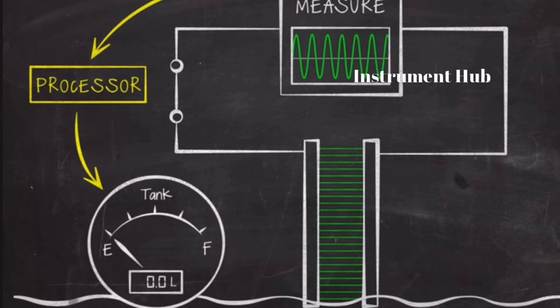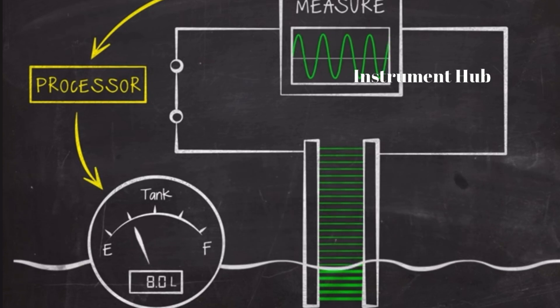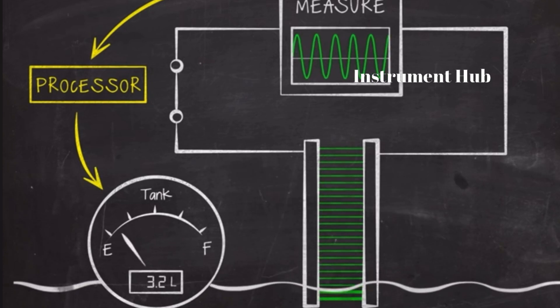This principle is calculated by our controller to process the actual level. For sensor calibration, we perform from the bottom level. If the bottom level is there, we calculate the low level. When the high level comes, we set the span. This is the sensor calibration — once the data is set, it will work according to the variation of the level.